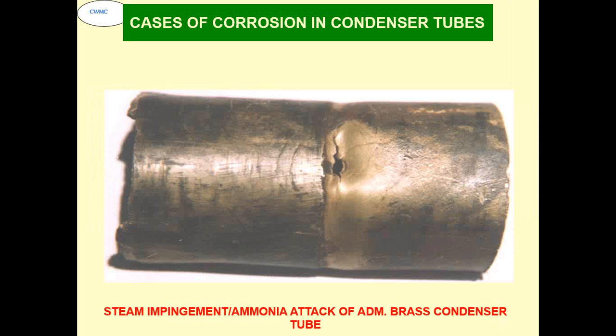admiralty brass condenser tube. Normally, on the boiler side, we give a treatment of ammonia. Now that ammonia, when it comes to the condensate, starts trickling down on the condenser tube, and if it is a brass tube, at the baffle point it starts concentrating, and then ultimately it will lead to the corrosion of the condenser tube. That is known as the steam impingement, ammonia grooving.